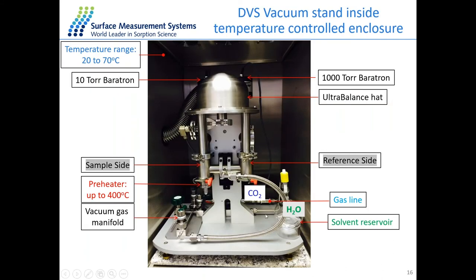The system can also run in static mode, similar to manometric systems, where we rely on the balance to continuously record changes in the weight of the sorbate. There are two sets of MFCs: one for pure water vapor with a solvent reservoir, and one for gases. This allows multi-component adsorption experiments by mixing water and CO₂ in different flow ratios, or by performing static water-CO₂ measurements where you first saturate the sample with water and then bring CO₂ on top.